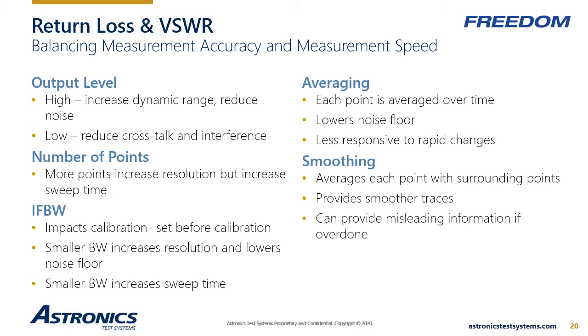The last parameter is smoothing. Rather than time averaging, this parameter averages adjacent points in each sweep, providing a smoother trace. This will improve the readability of the plot, especially for documentation purposes, but it is at the expense of resolution. Keep in mind that important data points indicating potential issues may be easier to overlook. Each parameter provides great control to maximize the effectiveness of the tool, but must be balanced according to the needs of the application.